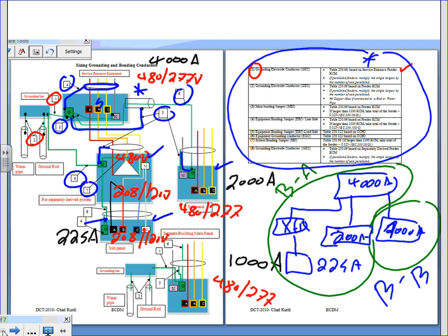We're sizing this right here and this right in here to the conduit going to the 2,000 amp switch gear. This one, I'm not going to size it to the transformer. If I want to size the one that's going to a transformer, I need the main that's coming to the transformer. I don't have that. Can you guys see where this number 5 is? This is tying this conduit to the 2,000 amp switch gear conduit to the grounding bar from both sides.